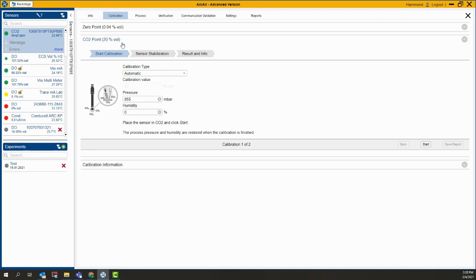There's a couple things here that are good to note. One is that you need to have this in 20% by volume CO2, and I recommend that you start flowing CO2 on the sensor here, and that's what I'm going to do right now. So we'll start to see our actual CO2 value going up here. And what should be done is let CO2 flow on the sensor at 20% for about 5 minutes before you start your cal. That will ensure that you get a good calibration.